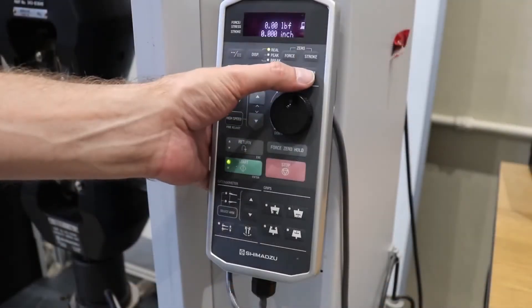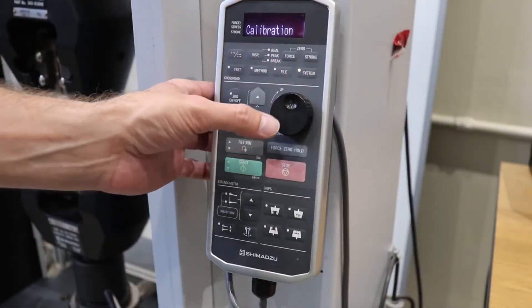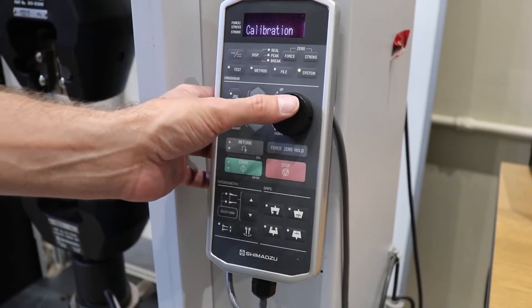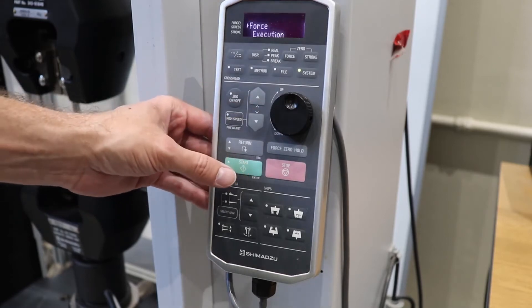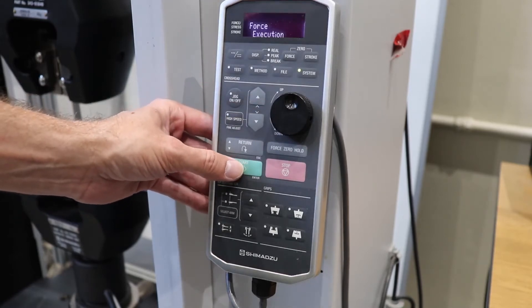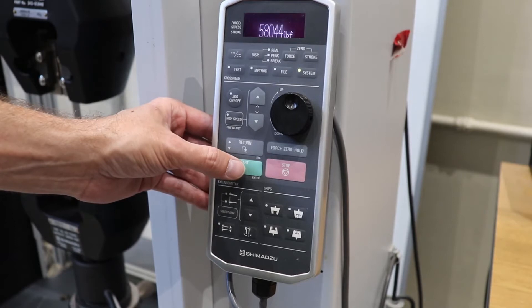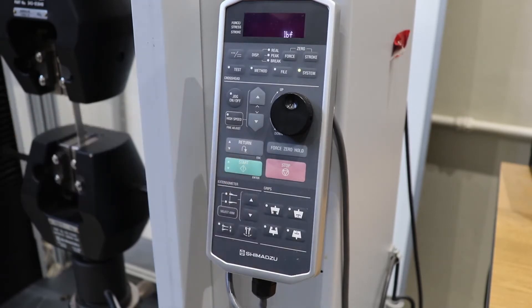Now we will go about calibrating the machine. To do so, we click System, press Start, Force Execution should pop up, and press Start again. This process takes a moment, please be patient. Once the process completed, Force Execution will show up on the screen. Simply press the Test button.